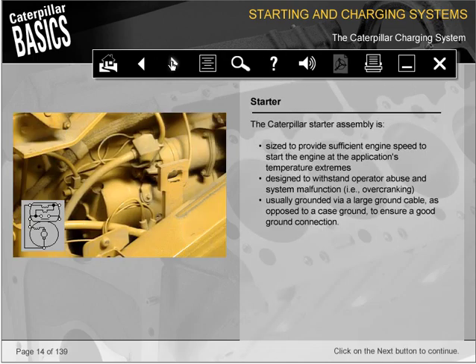The Caterpillar starter assembly is sized to provide sufficient engine speed to start the engine at the application's temperature extremes. It is designed to withstand operator abuse and system malfunction, for instance, overcranking. It is usually grounded via a large ground cable, as opposed to a case ground, to ensure a good ground connection.